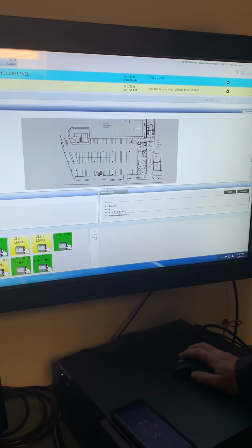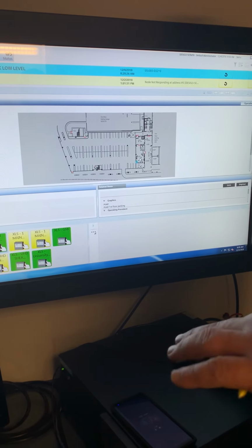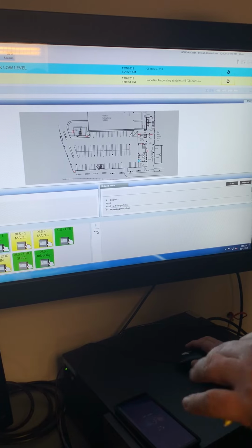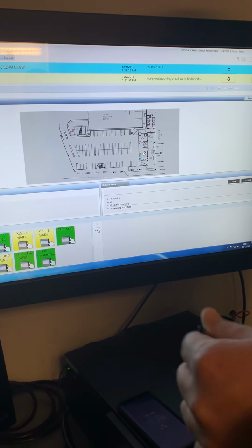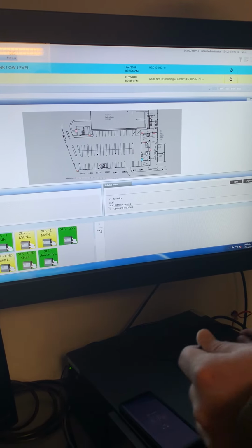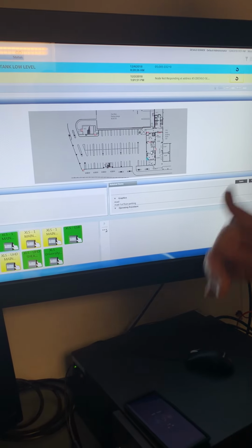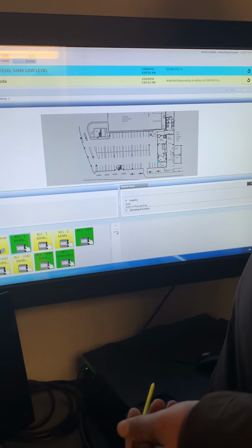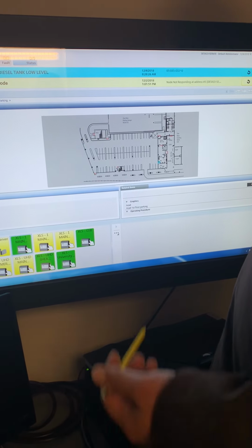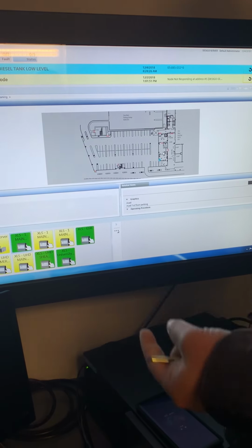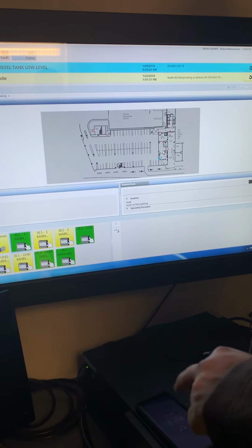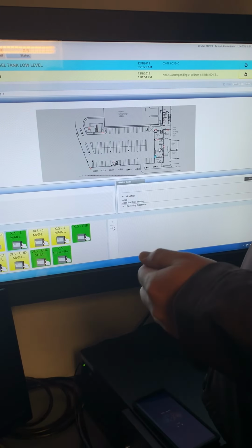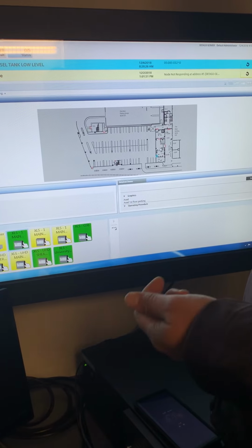Supervisory just means it's active. That point is active, but it's not setting off any AVs or anything. So it's just a step down from an alarm. It just needs to be investigated, just telling you there's minor issues. Your supervisories are like duct detectors and tampered items. If you have a valve closed, it's a supervisory.